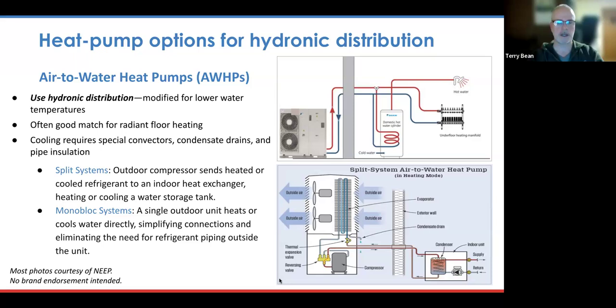What's changed recently with some of these systems is that the water temperature with some of the newer systems can get high enough where they don't necessarily need radiant floor heating or radiators. They can actually work with baseboard. We saw one recently in Melrose that was able to do that. So what the system in Melrose looked like was, he was able to use his baseboard hydronic distribution for the heating aspect of an air-to-water system, but he still needed a high velocity 2-inch flexible ductwork system to handle the cooling aspect, so that you could also handle the condensate, and that also amended some of the heating supply.